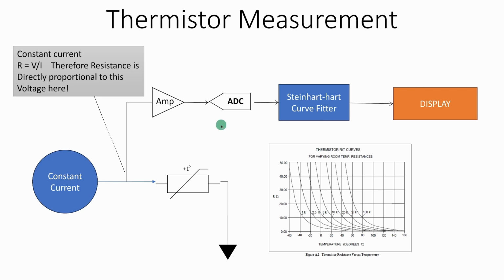So in terms of what could have gone wrong, well, an obvious thing that could have gone wrong is this constant current source. If we're outputting the wrong current, then the voltage is going to be wrong. And if we think about the errors, we got error 2, which basically means I've measured the voltage, I've passed it through the amplifier, and I can't turn it into a sensible value. It doesn't make any sense. I can't solve the temperature given the resistance that I'm measuring. That then turned into error 1, which basically says the ADC is over range. So that would indicate three possible places. 1, the constant current isn't what it's supposed to be. 2, there's actually a break or short circuit around this thermistor, so we don't have the resistance we're expecting. And 3, this amplifier is doing something stupid with the actual voltage. Now all this stuff's connected together, so of course it could be something a little bit more subtle than that, but certainly measuring the constant current is going to be my first step.